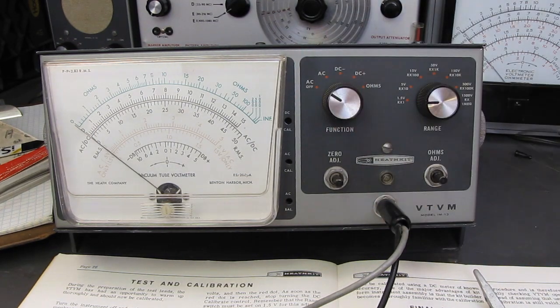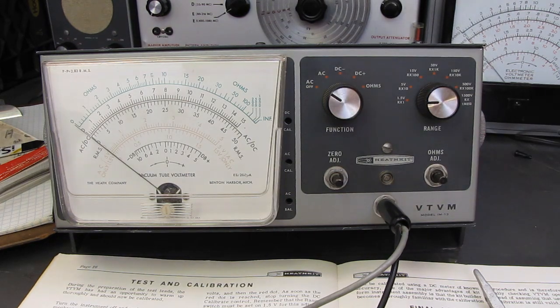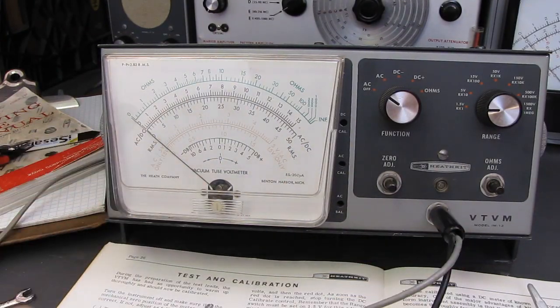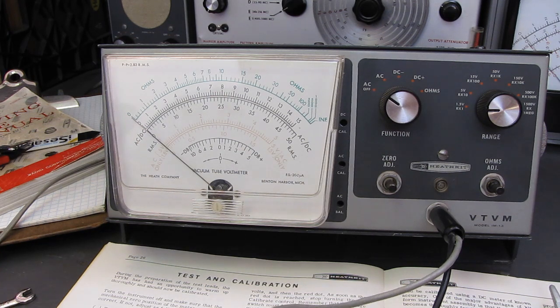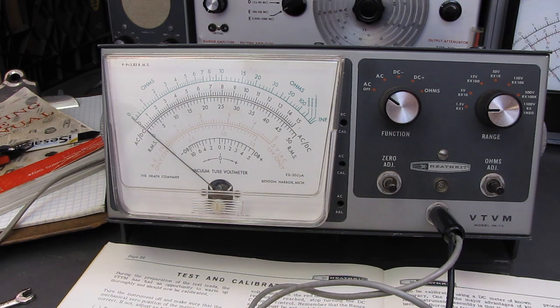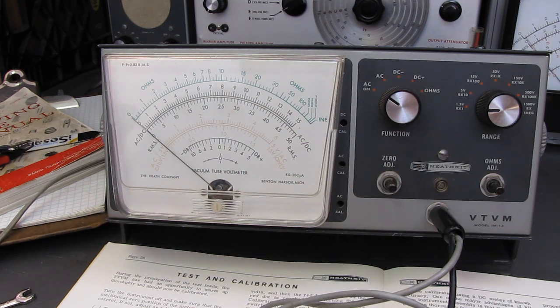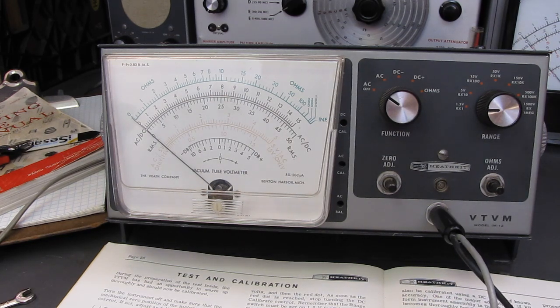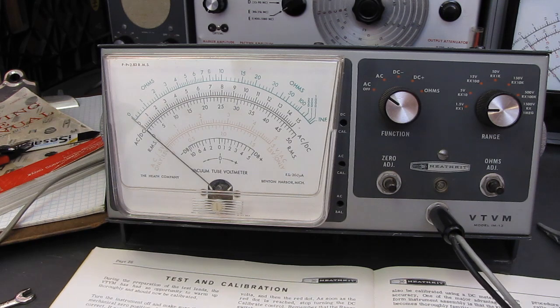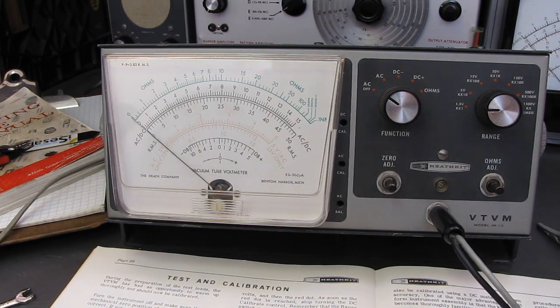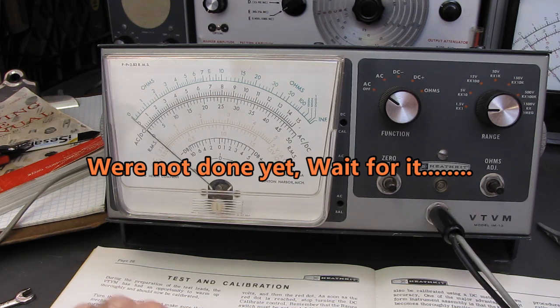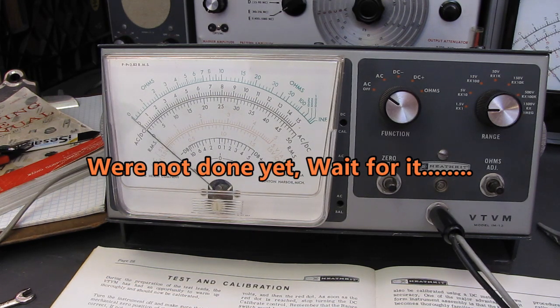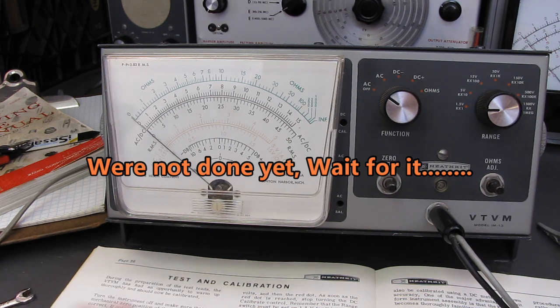As far as I'm concerned, that's fixed. That is a repaired Heathkit IM13 VTVM. So if your meter begins to act erratically like that, swinging back and forth, it's just possible that you have a heater to cathode leak. And one of the quickest things to do is just swap it out for a known good tube and see if that problem goes away. And on this one it did. And it's funny. I woke up about 2 a.m. last night thinking about this and I said, I bet the tube's got a heater to cathode leak. And it did.